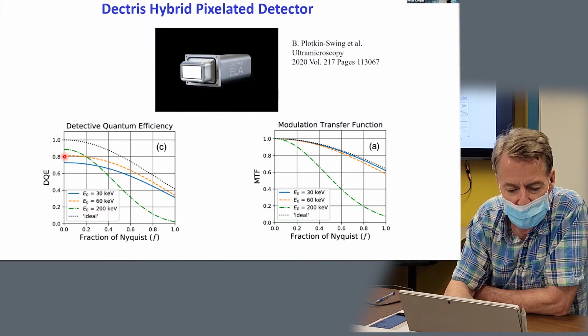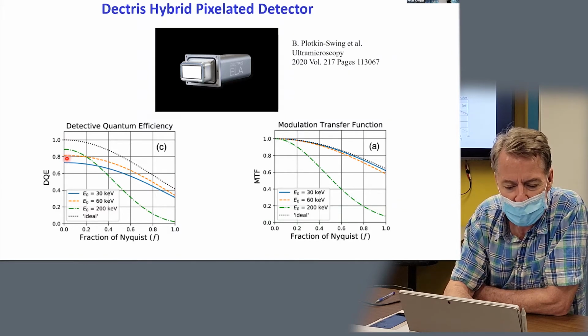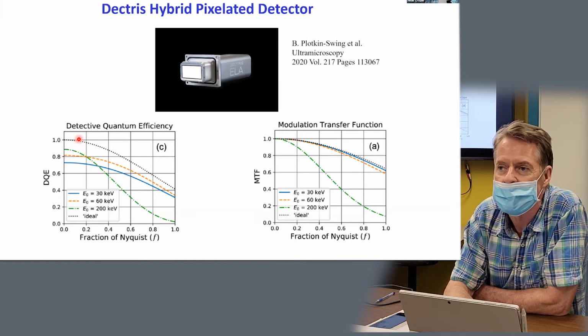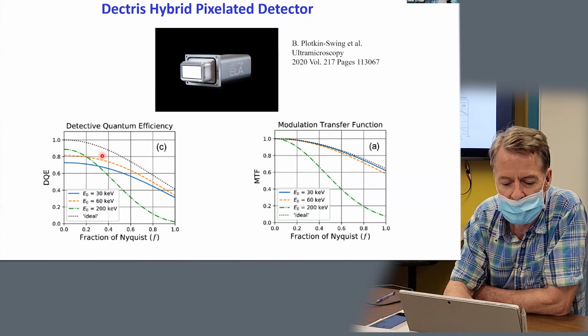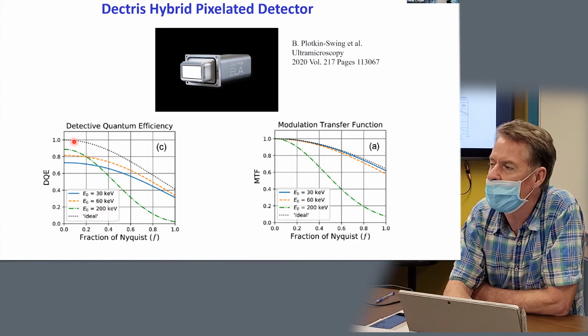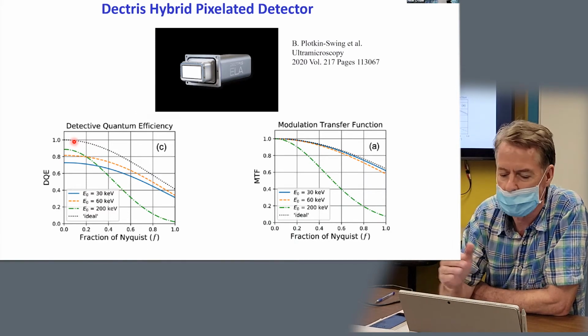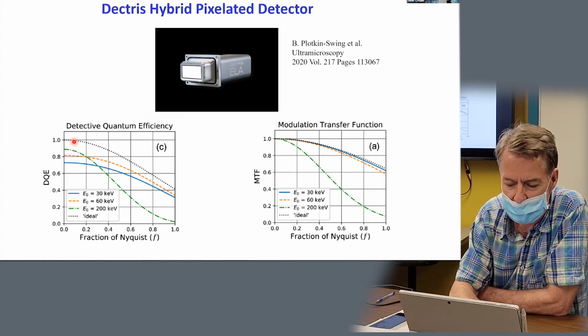What I want to point out is that our microscope running at 30 or 60 kV, if you look at the yellow curve and the blue curve, they're almost matching the theoretical maximum. So the differences in efficiency that we have on our detector are on the order of less than 20% away from the theoretical maximum. So that's really fabulous performance.